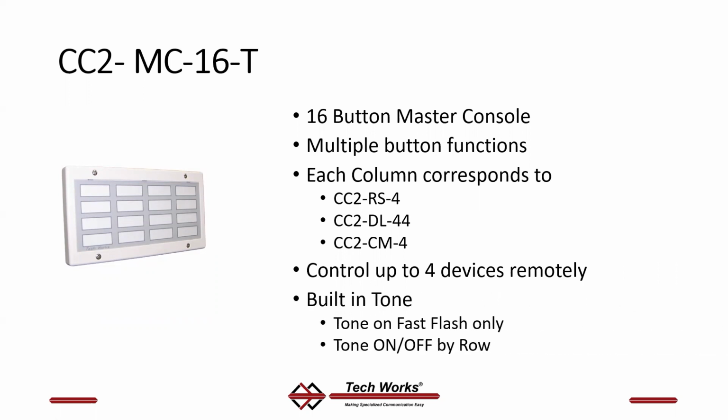Built-in tone. Why would you want a tone on this? Because if you've got something going on out in the field like a control module, this becomes an annunciator as well. And again, you can turn that tone on and off. You can set how it functions, but you might want to know that a refrigerator door got shut somewhere.